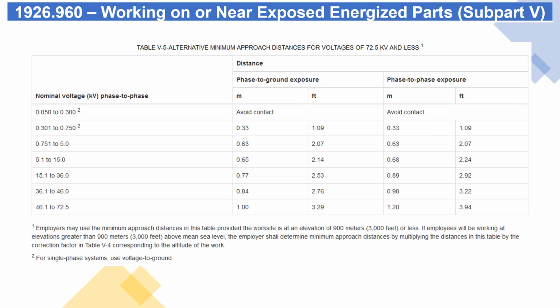Table V5, alternative minimum approach distances for voltages of 72.5 kV and less. Employers may use the minimum approach distances in this table provided the worksite is at an elevation of 900 meters, 3,000 feet, or less. If employees will be working at elevations greater than 900 meters, 3,000 feet, above mean sea level, the employer shall determine minimum approach distances by multiplying the distances in this table by the correction factor in Table V4 corresponding to the altitude of the work. For single-phase systems, use voltage to ground.